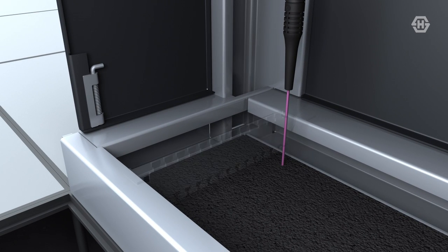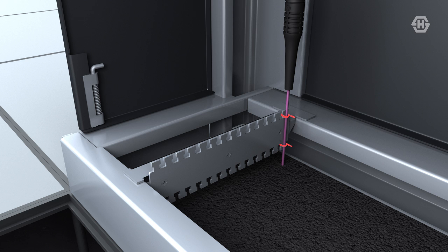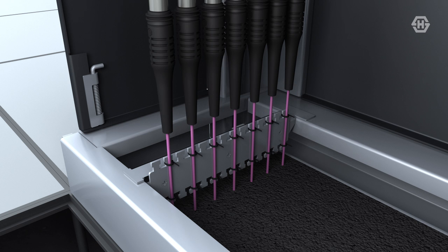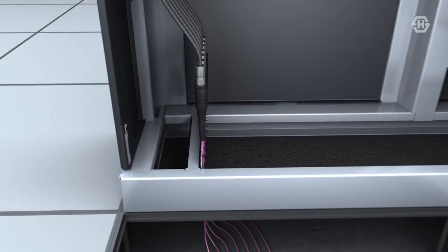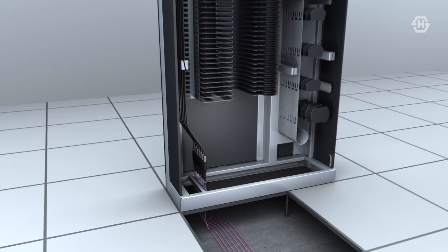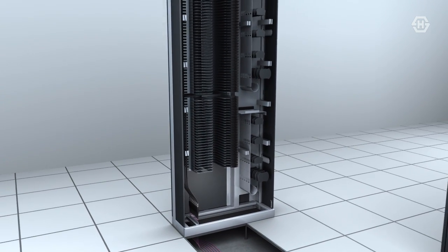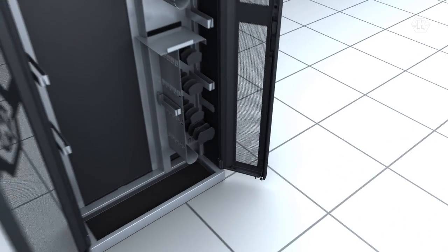And in this case, Huber+Suhner recommend a simple tie-off plate where only the outer jacket of the cable is fixed to the rack. These tie-off plates can be placed directly against the inner wall of the NGR or mounted on a support rail, depending on the size and the quantity of the cables. All of our cable fixing solutions are designed to offer maximum protection to the cable and fast, easy access for the user. Cables can be added and removed at any time without disrupting live fibers. Our general principle is based on minimizing the point of failure so that each 12 or 24 fiber bundle is offered maximum protection. Let's take a look now at the connectivity hardware inside the cabinet.